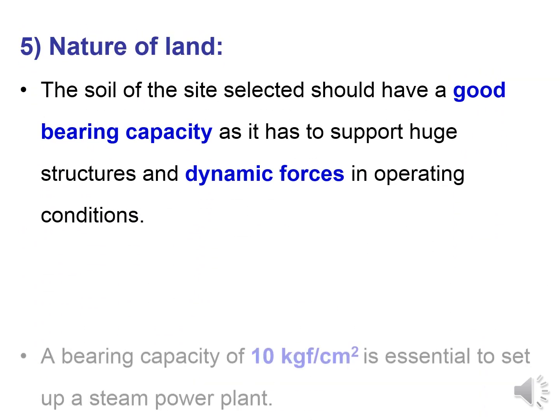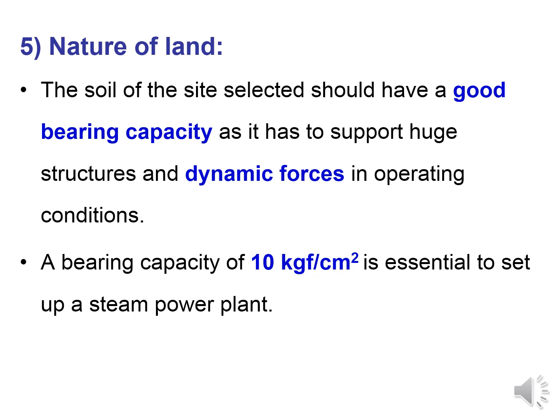The nature of land is very important. The soil at the selected site should have good bearing capacity to bear the large forces and structures situated on it. There are also dynamic forces in operating conditions. The bearing capacity should be around 10 kgf per centimeter square, which is essential to set up a steam power plant and to withstand huge structures and dynamic forces.